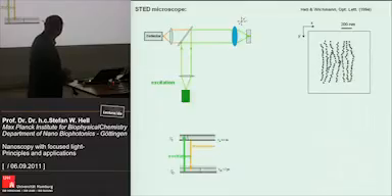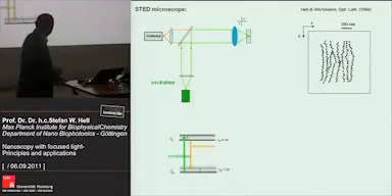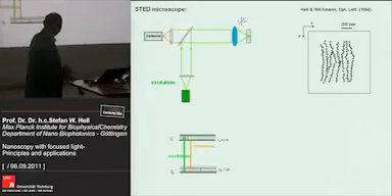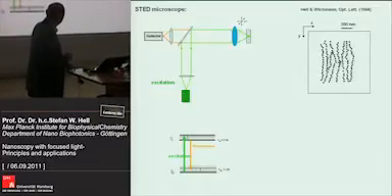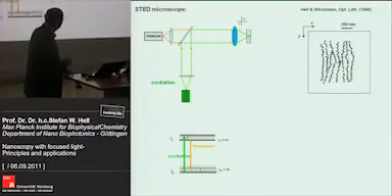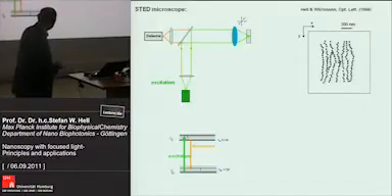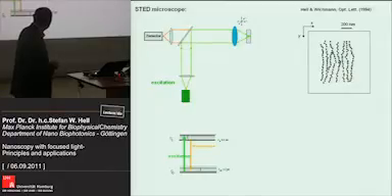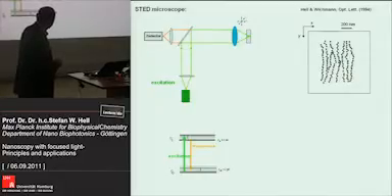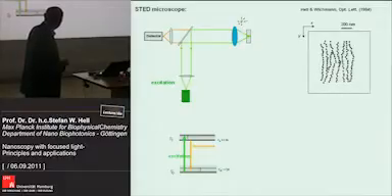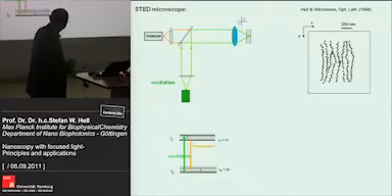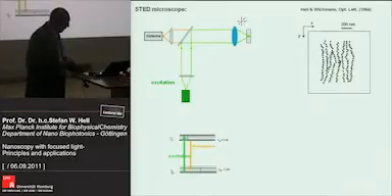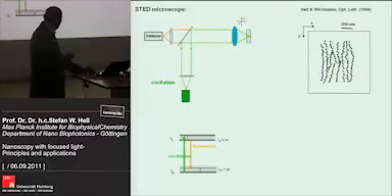We have a lens whose role is to focus light down to a point. A laser — an excitation light source — provides green light that bounces off a dichroic mirror, and the lens focuses the light down to the focal region to excite fluorescent molecules from their ground state to the fluorescent state. They dwell briefly in the lower-lying vibrational level of the first electronic excited state — about a nanosecond — then come down by emitting a fluorescent photon, which is collected by the same objective and measured at a detector.